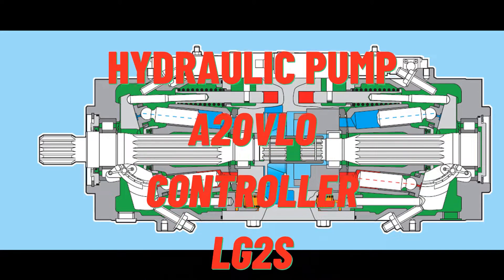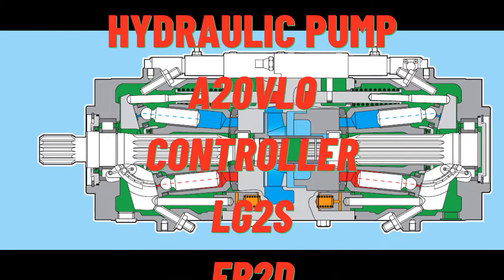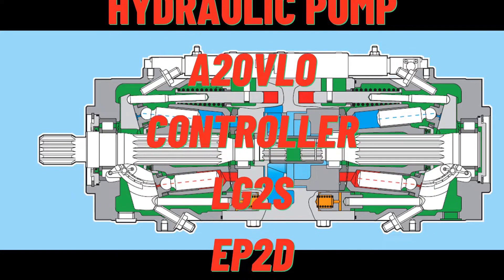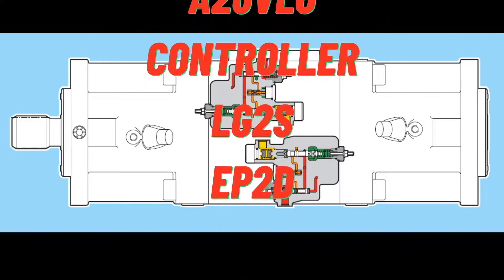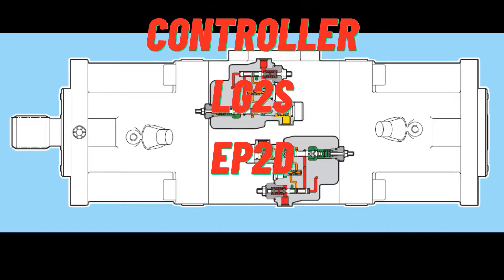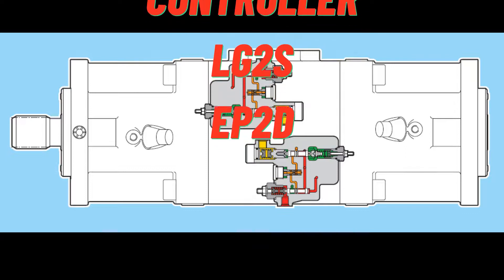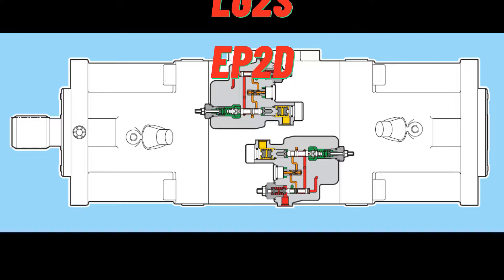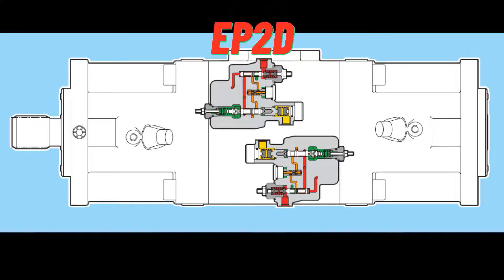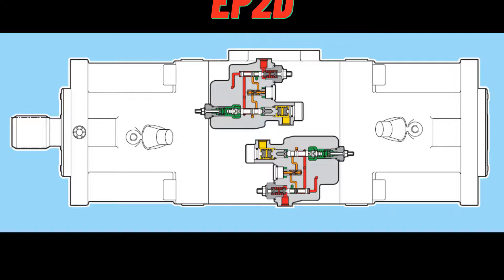Output flow is proportional to drive speed and pump displacement, and is steplessly variable between maximum and zero displacement. Further technical data is available for control devices C4. A11VO types of controllers. A20VLO, LG2S Constant Power Control. A20VLO, EP2D Electrical Proportional Control.